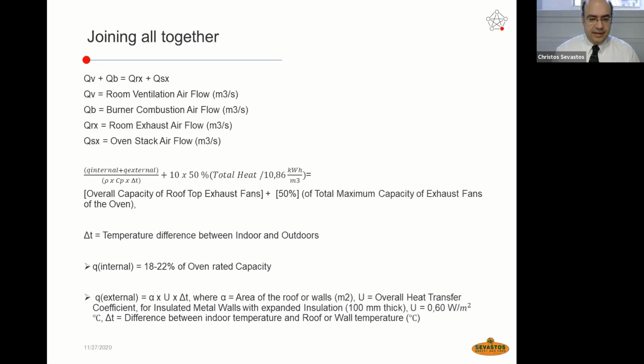Regarding the Q external, which is the other factor we need in order to define the air ventilation, it comes from the multiplication of the area of the roof and the walls by the overall heat transfer coefficient for insulated metal walls with insulation of 100 millimeter thickness. This is 0.6. We're taking some constants here in the equation. And delta T, the gradient of T, is the difference between indoor temperature and roof or wall temperature. This gives us the external heat.